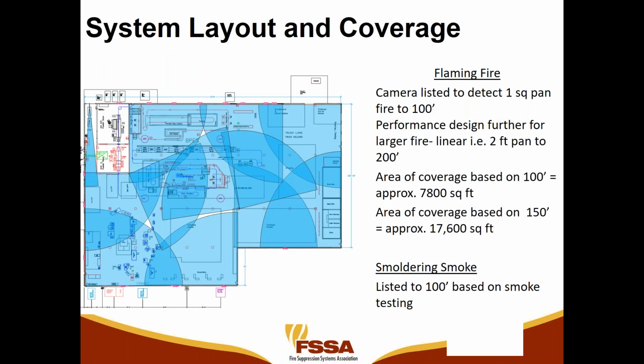So the way that we lay out video analytics systems, the field of view horizontally is close to 90 degrees. So we start in the corners to follow the 90 degrees of the wall. The detectors are listed to 100 feet based on a 4-minute smoke emitter or a 1 square foot pan fire. So we just lay down quarter circles covering the white space, of course, where we can mount the detectors, and we count the quarter circles. That gives us a camera count and tells us what size of NVR is required. Each camera will cover 7,800 square feet based on a 100-foot radius.